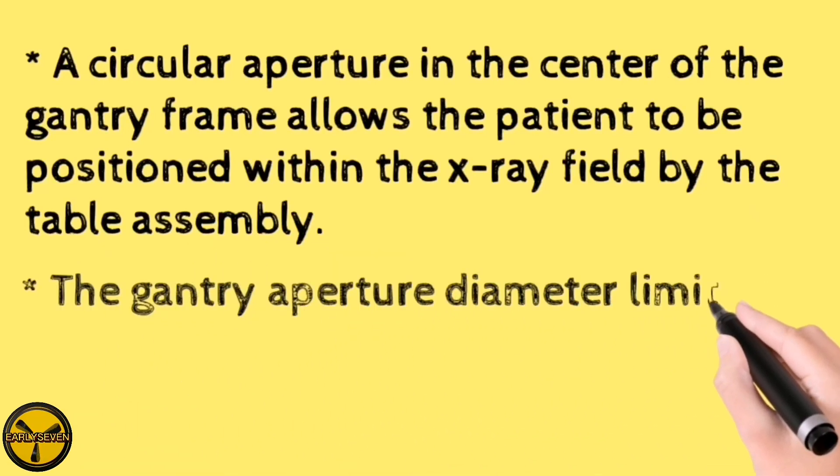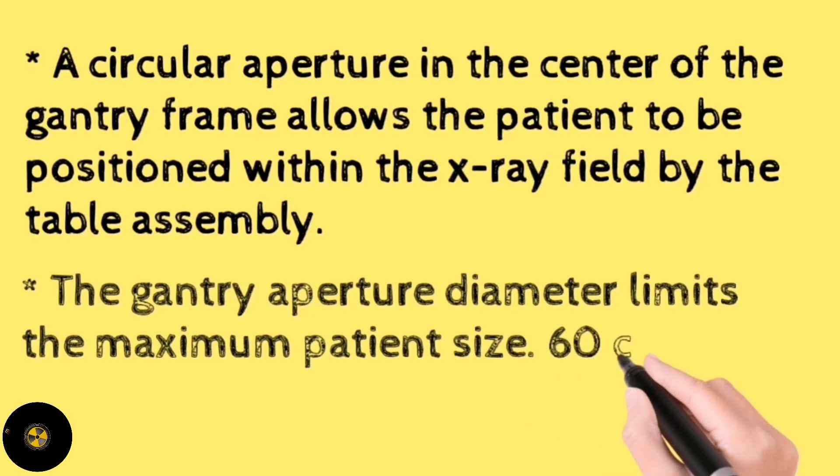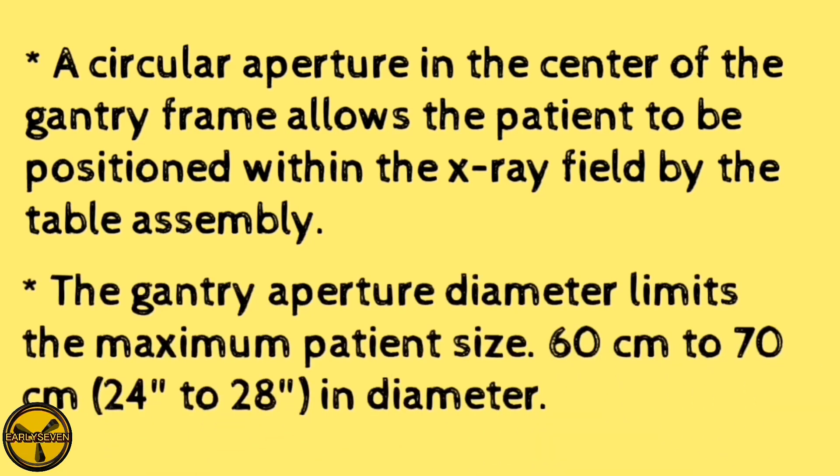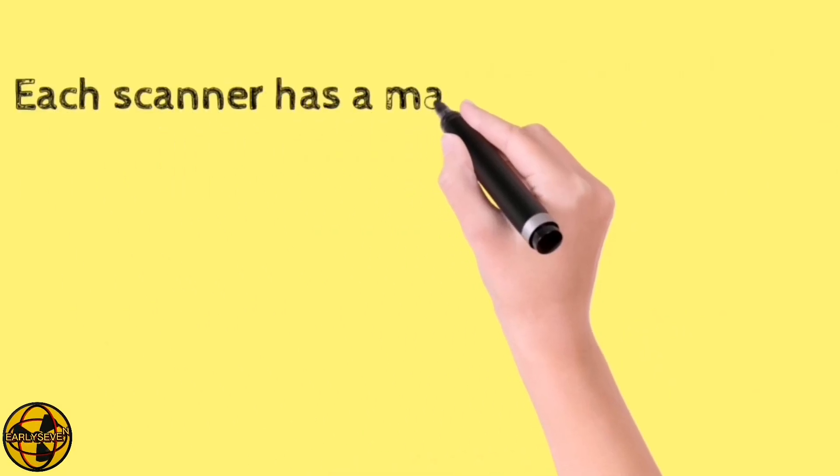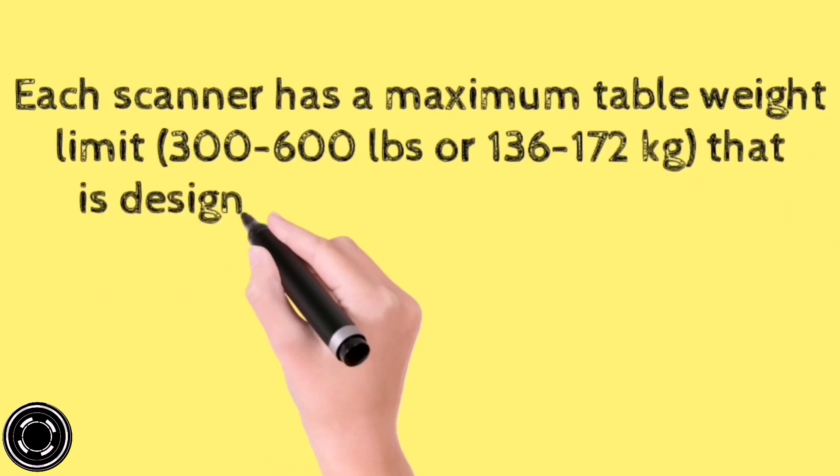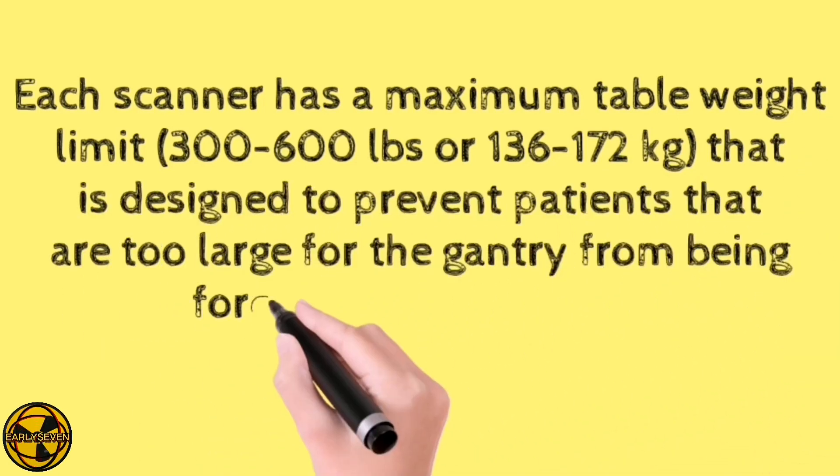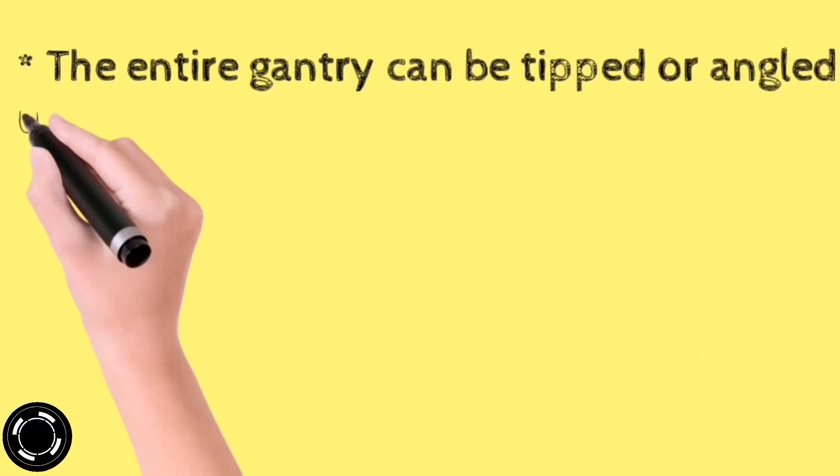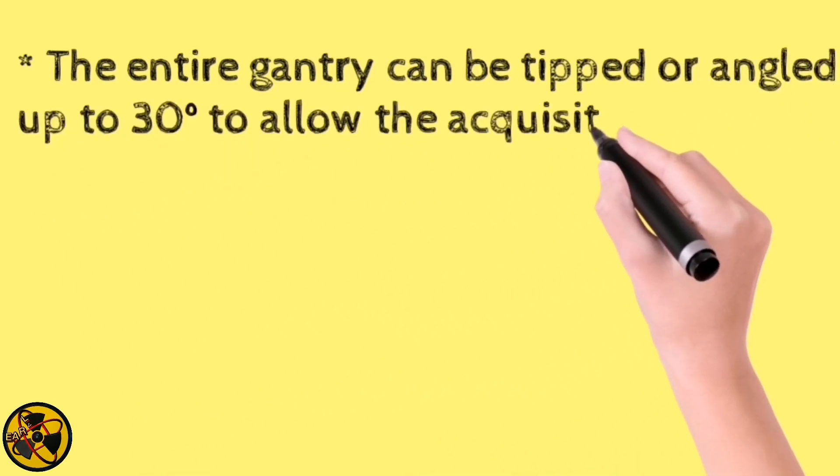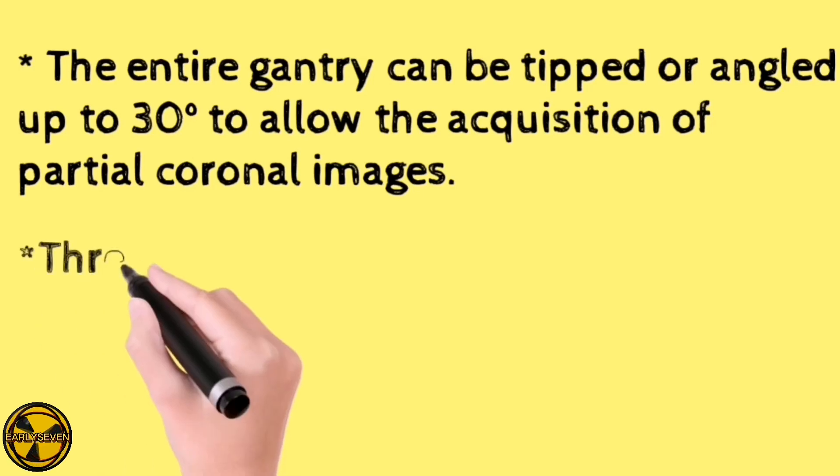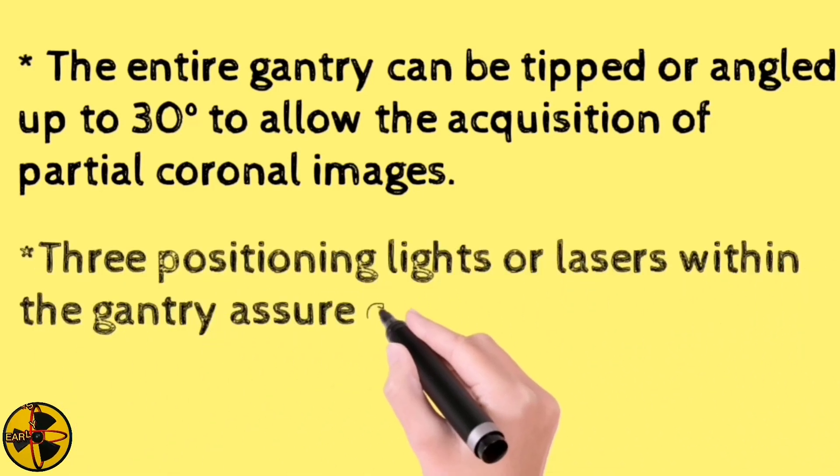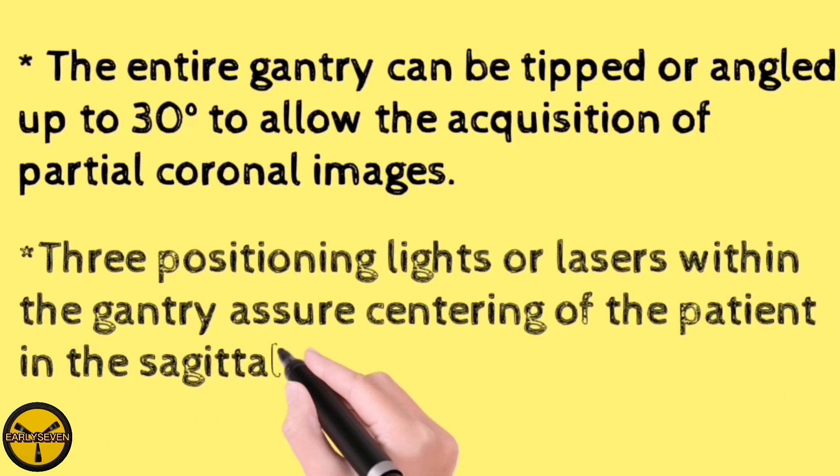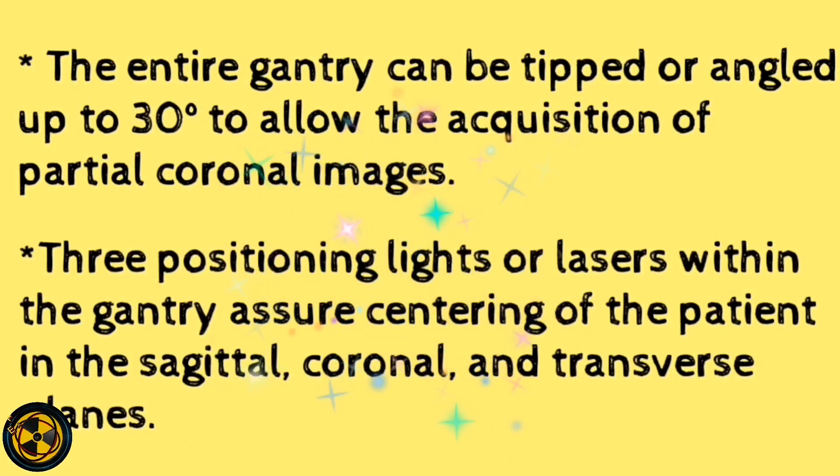The gantry aperture diameter limits the maximum patient size which is 60 cm to 70 cm or 24 to 28 inches in diameter. Each scanner has a maximum table weight limit of 300 to 600 lbs or 136 to 172 kg that is designed to prevent patients that are too large for the gantry from being forced into the scanner. The entire gantry can be tipped or angled up to 30 degrees to allow the acquisition of partial coronal images. Three positioning lights or lasers within the gantry assure centering of the patient in the sagittal, coronal and transverse planes.